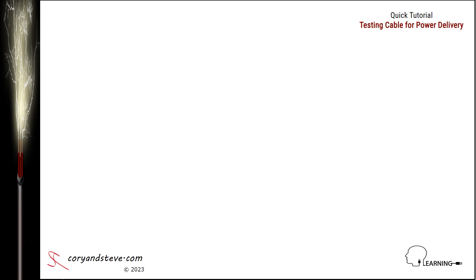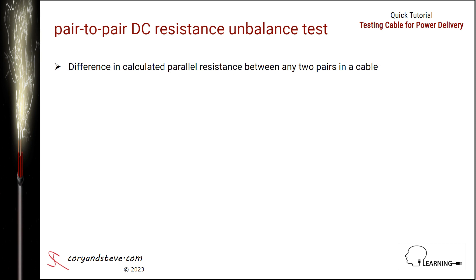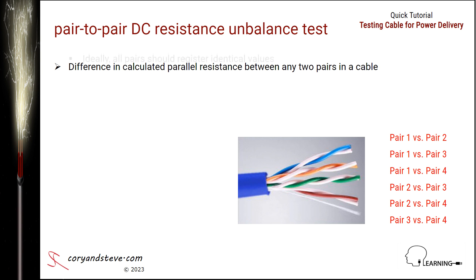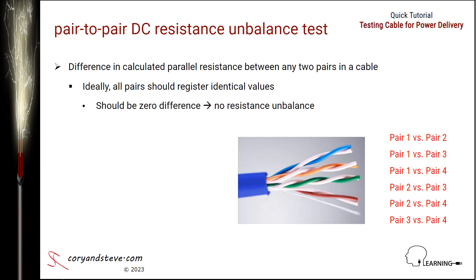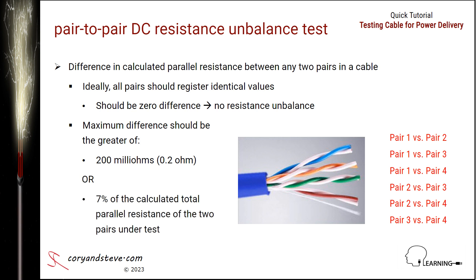Next, we'll conclude with the last of the three DC resistance tests: pair-to-pair DC resistance unbalance. This parameter is also called DC resistance unbalance, but here it's measured between any two pairs in a cable rather than between the two conductors of any single pair. Note that there are six possible combinations: pair one versus pair two, one versus three, one versus four, two versus three, two versus four, and three versus four. Ideally, all pairs should register identical values with zero difference between any of the pairs. But in the worst case, the difference should be no greater than 200 milliohms or 7% of the calculated total parallel resistance of the two pairs under test, whichever is greater.